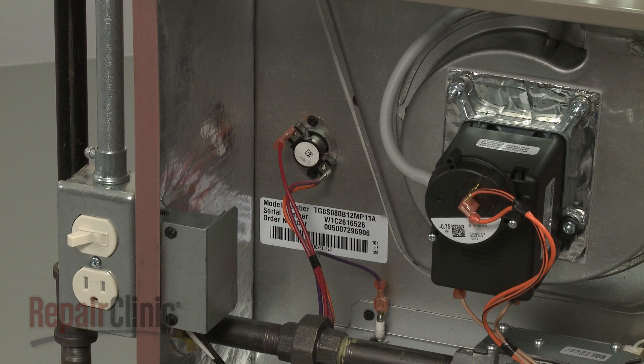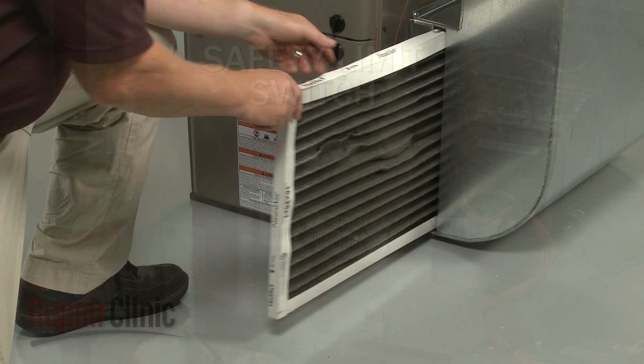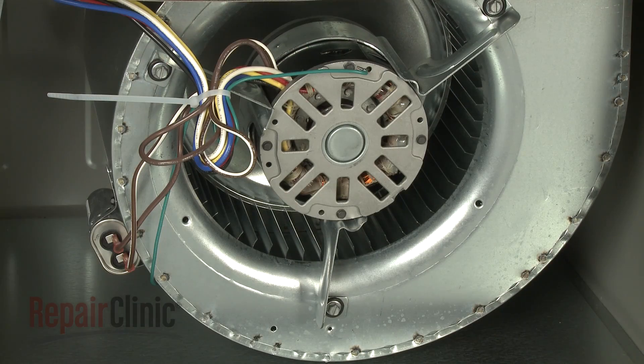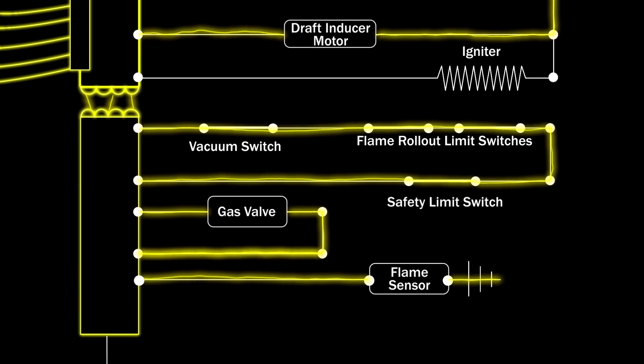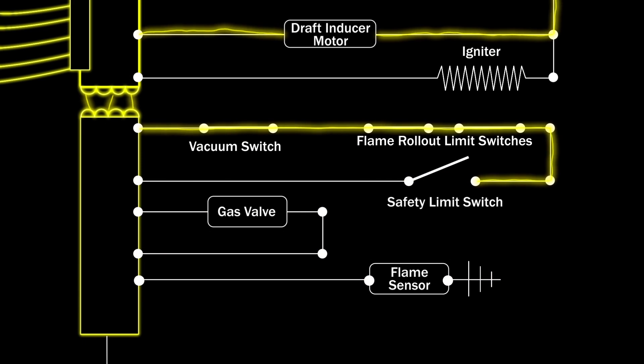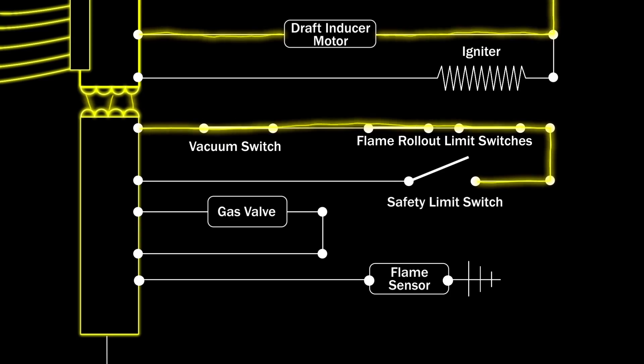Mounted near the heat exchanger is a safety limit switch that monitors the air temperature. If the filter is clogged or the circulation blower fan motor fails, the heat exchanger will overheat. The limit switch will open and the control board will shut off voltage to the gas valve to prevent damage to the furnace.